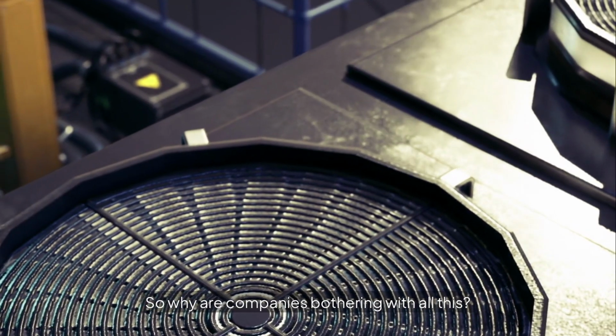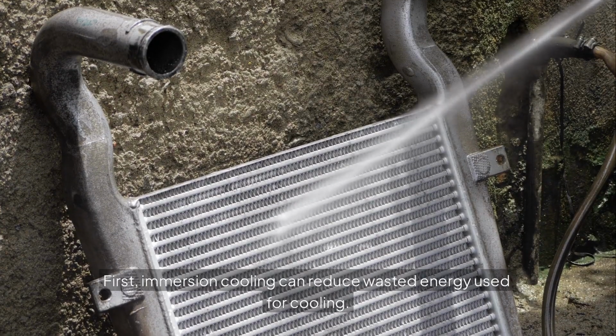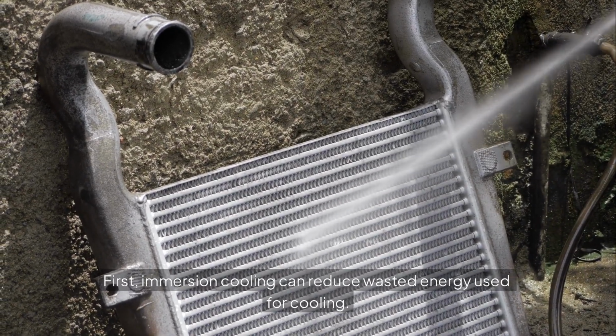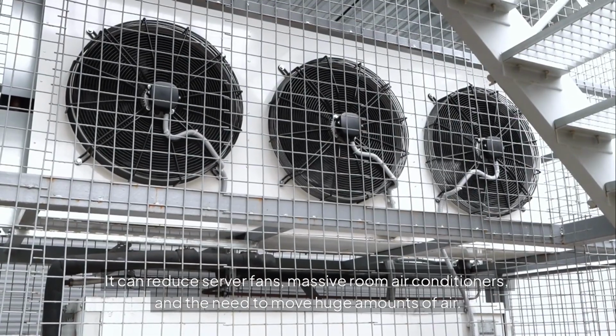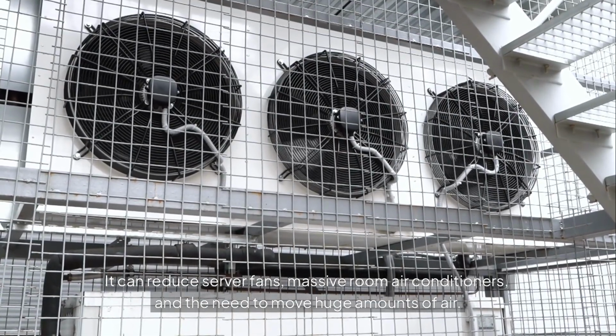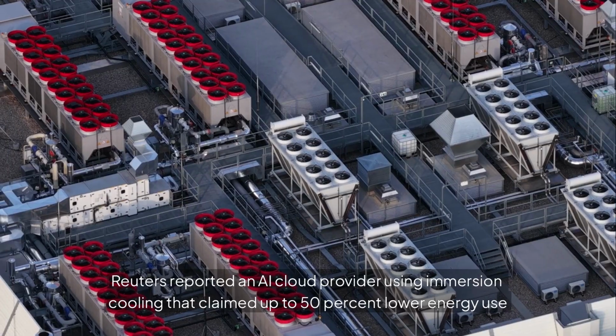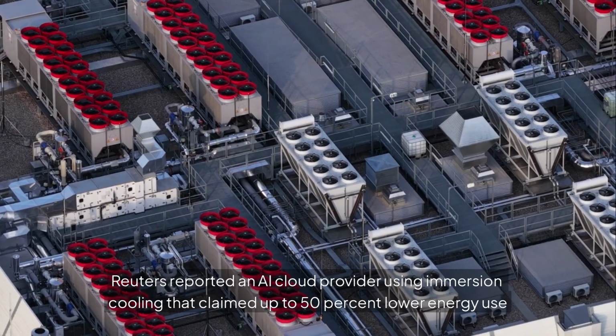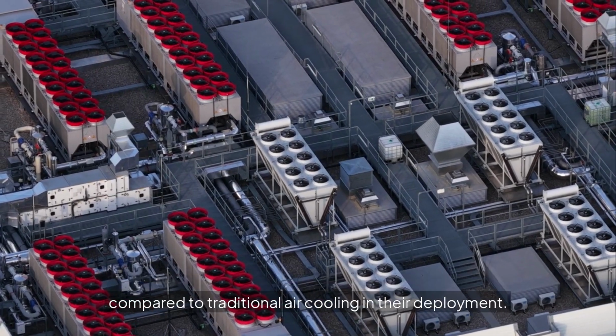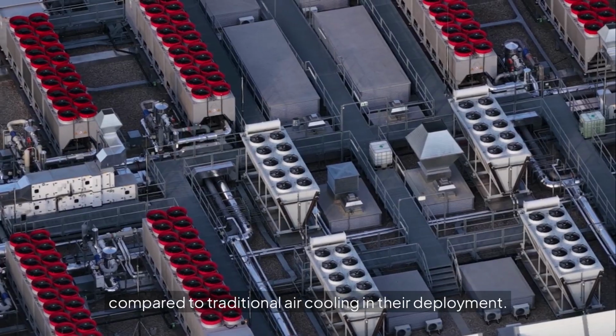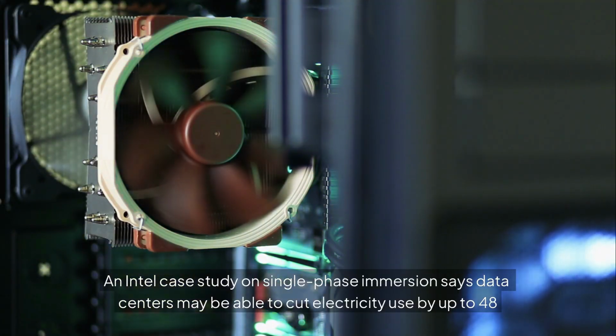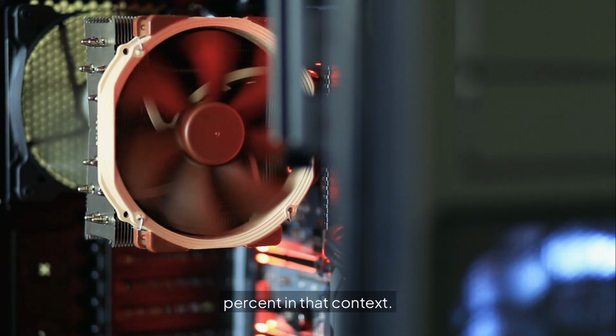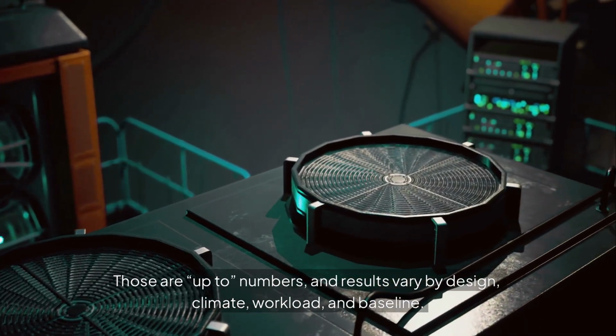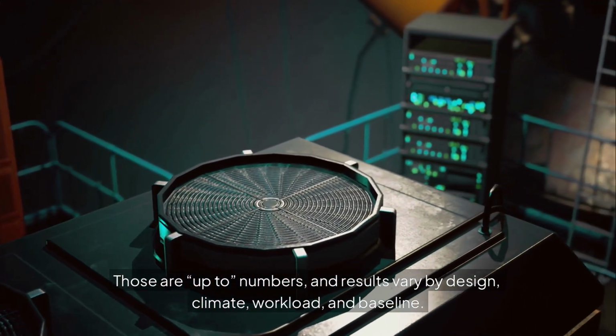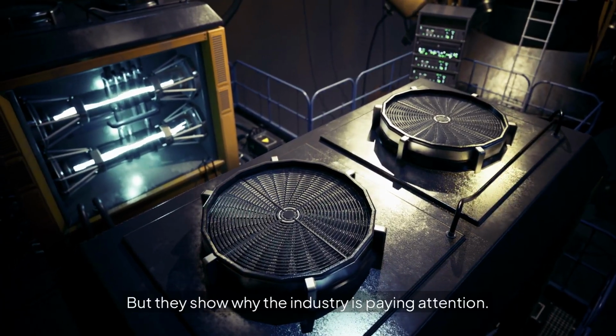So why are companies bothering with all this? First, immersion cooling can reduce wasted energy used for cooling. It can reduce server fans, massive room air conditioners, and the need to move huge amounts of air. Reuters reported an AI cloud provider using immersion cooling that claimed up to 50% lower energy use compared to traditional air cooling in their deployment. An Intel case study on single-phase immersion says data centers may be able to cut electricity use by up to 48% in that context. Those are up to numbers, and results vary by design, climate, workload, and baseline. But they show why the industry is paying attention.